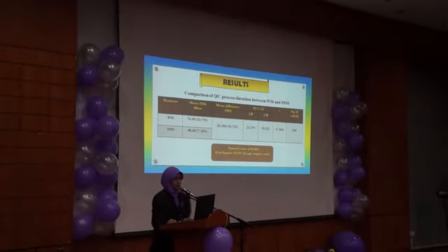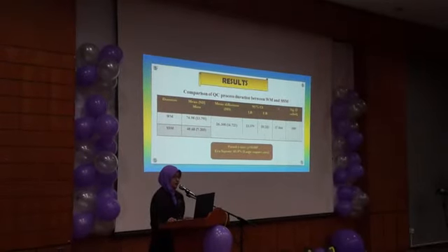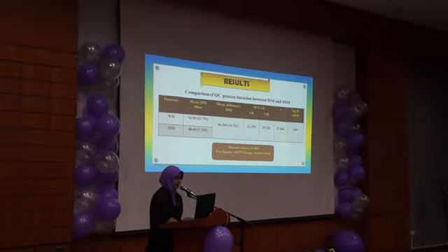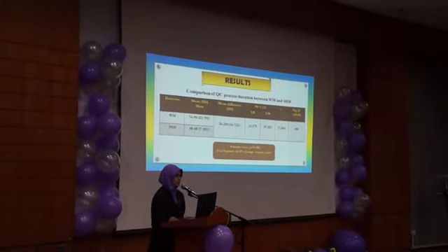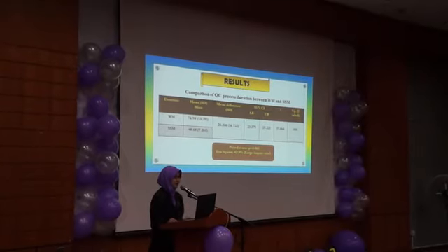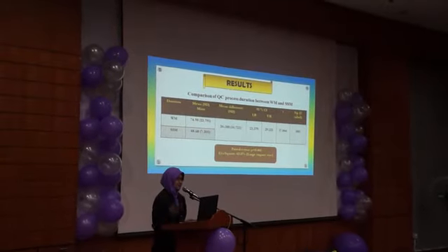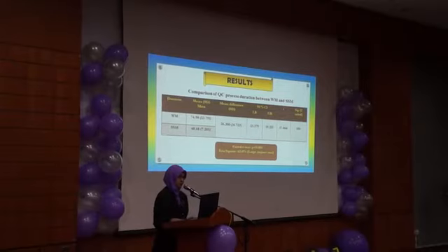So for comparison of QC process duration, there is also a significant decrease, with a mean difference of 26 minutes. Because for some analytes, we don't need to do the QC twice a day, and that contributes to less time for performing QC.